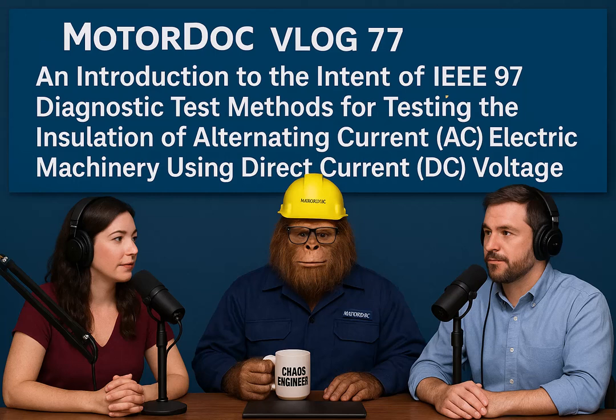Okay. So at its core, insulation testing for these big AC rotating machines is about assessing the ground wall insulation. The ground wall. Yeah. That's the main barrier. Yeah, think of it like the primary barrier. It's the high voltage wall separating the copper conductors, carrying all that power, from the machine's grounded frame. Right. And the traditional DC tests, like the ones in IEEE standards for insulation resistance, IR, and polarization index, PI, or maybe DC overvoltage tests. Those are great for a quick check. Will it handle a basic stress test? Is its resistance high enough? They give you that essential answer: can I re-energize this? Okay, the basic safety check.